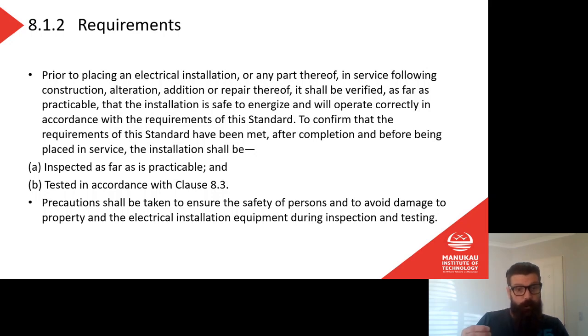An example of something that would not be practicable is that if I go to a new house and I do all the wiring, I put all the wiring in the walls before the walls are on, so just framing, and I know that it's all safe and everything's good because I've done it. When I come back to do the fit off and then test it before I turn it on, presumably the walls have been put on, I can no longer see those cables. So this part of the standard does not require us to then go and rip all the walls out so I can look at the cables before I turn it on. It allows us to assume that if the cables were good when we put them in, we assume that they're good now. They may not be.